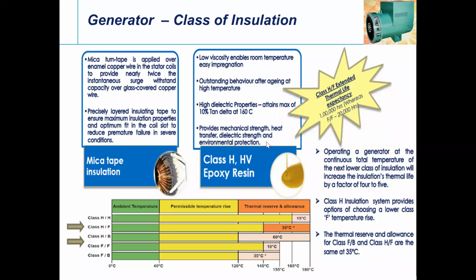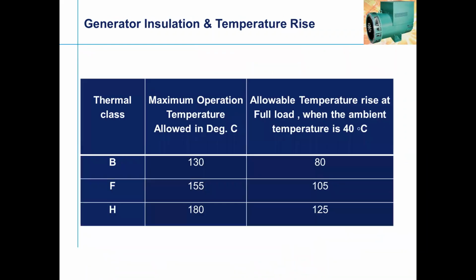And moreover, the generator is going to develop a low voltage up to 415 or a high voltage up to 11 kV. The insulation scheme is very, very important. That's what we have been giving to the market. So to have a common understanding, to put it in perspective, one is thermal class B, where the maximum temperature allowed is 130 degrees, and the allowable temperature rise from ambient is up to 80 degrees. This is why we are talking about that.